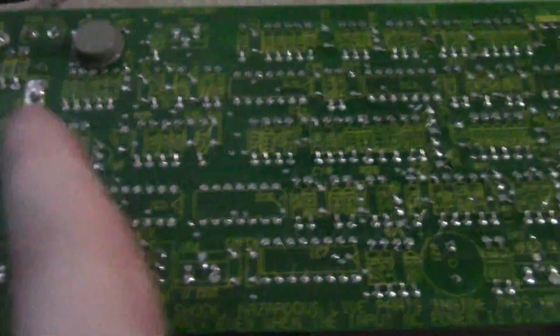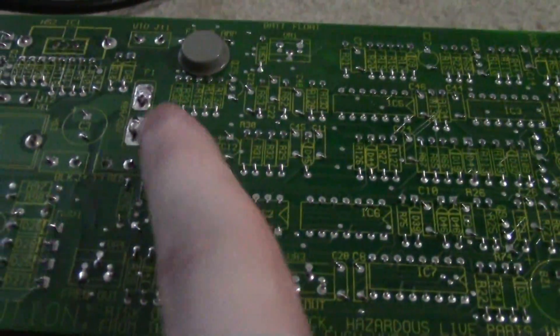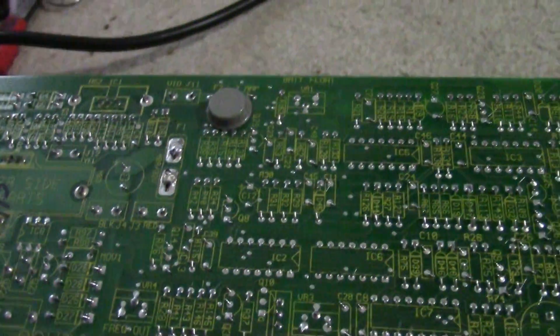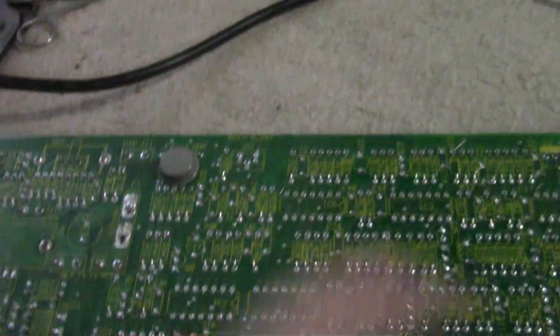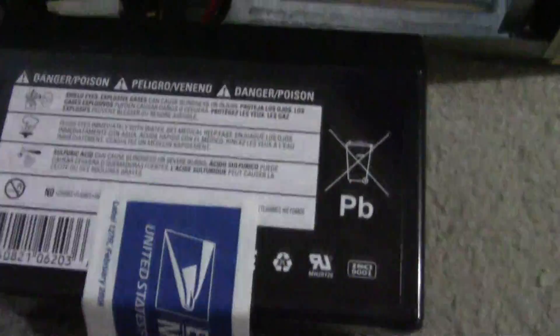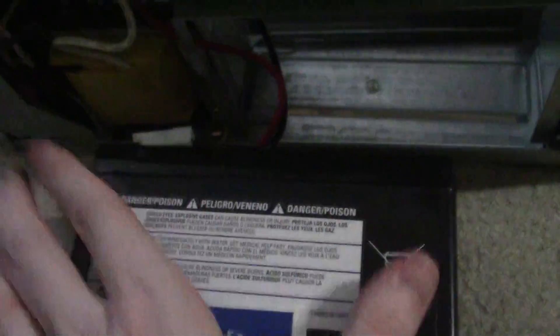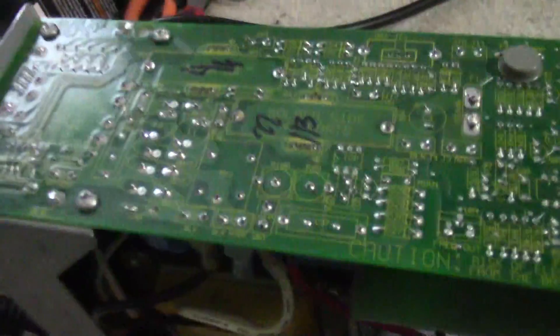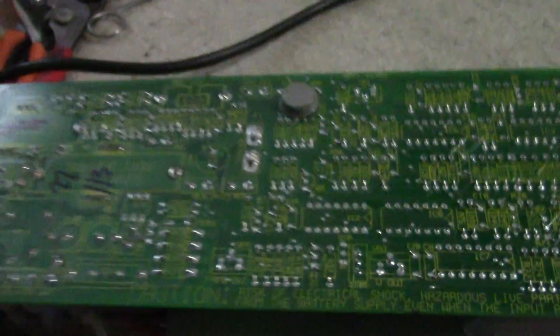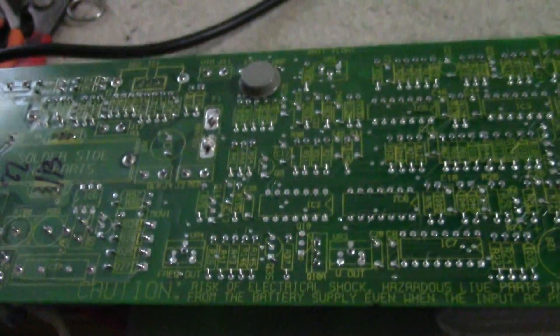So that is how you fix a UPS that won't run off battery power. That's what I figured it was, just an open circuit. This main ATC fuse on the board here was blown, so I just replaced it. If anyone else out there has a UPS and they're finding that it won't run off the battery, consider opening it up and checking the fuse on the board.